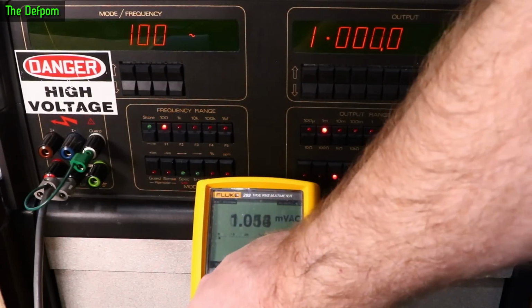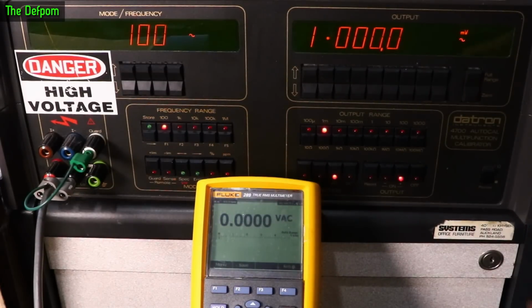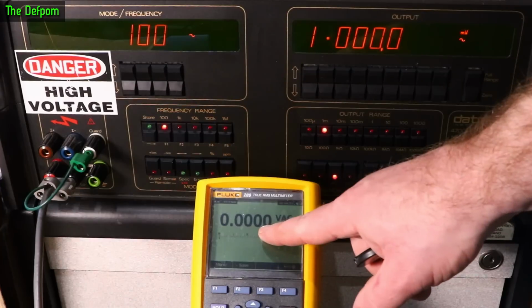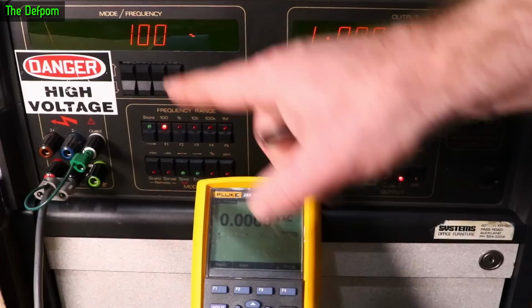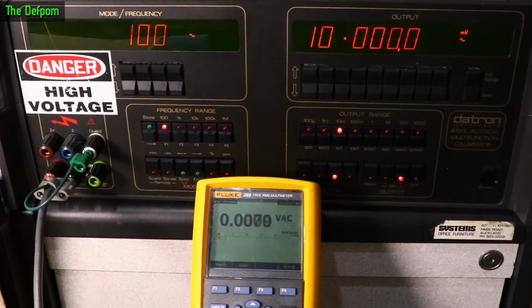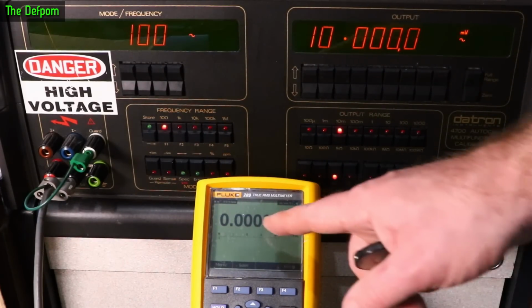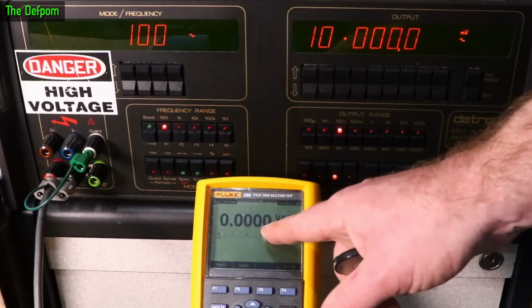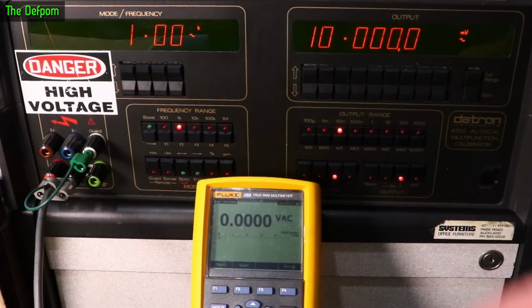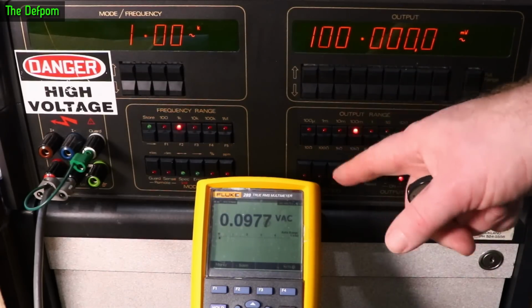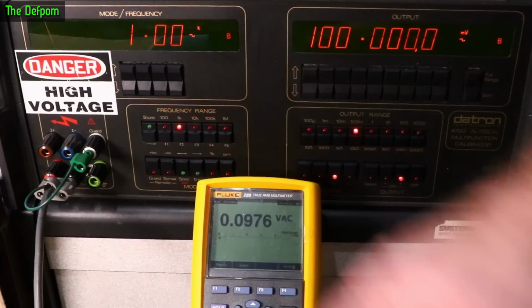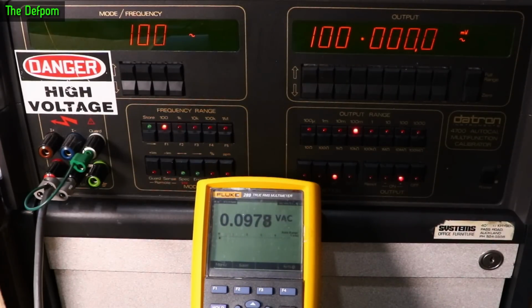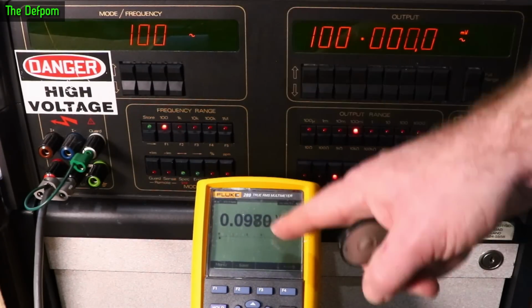So let's switch to the AC range on the actual main voltage. So 1 millivolt should be showing 10 counts on here. And we're not seeing it at 100 hertz. Let's try 10 millivolts. And we're still not seeing it. Okay, I would have thought I would be able to see 10 millivolts, seeing as it actually has that resolution. Let's change frequency to 1K in case it matters. No, it didn't help. So 100 millivolts at 1K is reading about 20 counts down. So that's why we couldn't see the 10 millivolts, because it's below that. It's being rounded off to 0. So also the very bottom voltage calibration is a little bit off. And 100 hertz is the same.